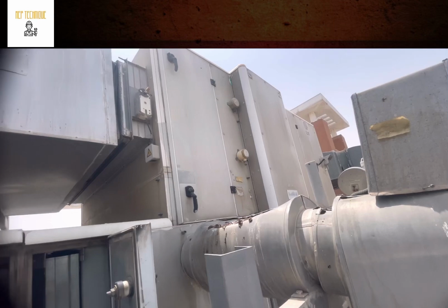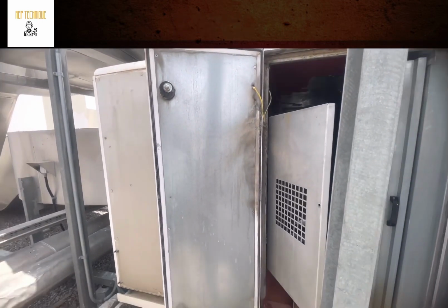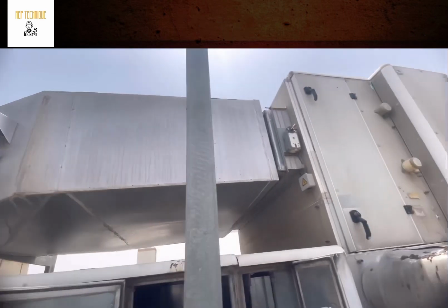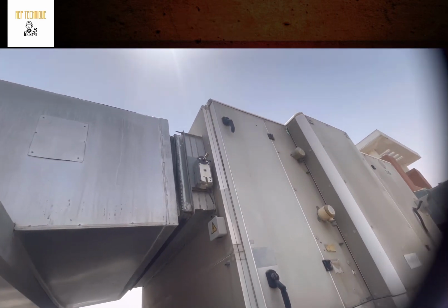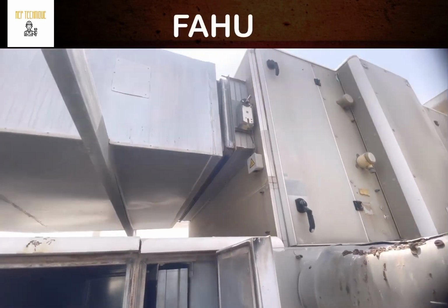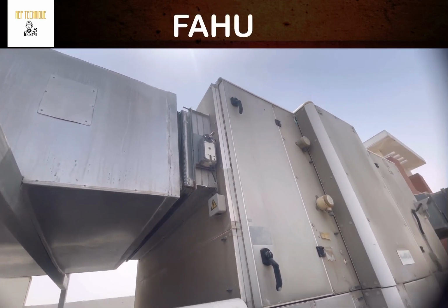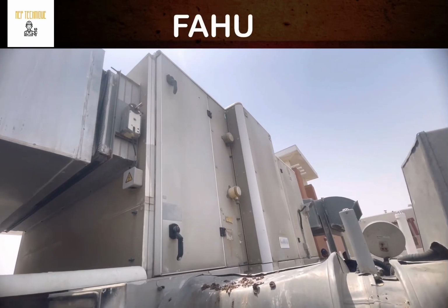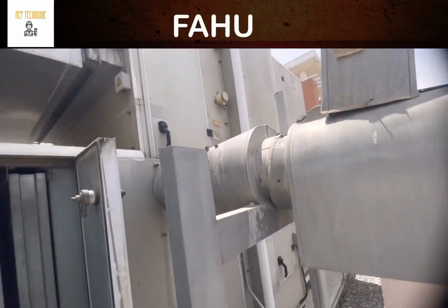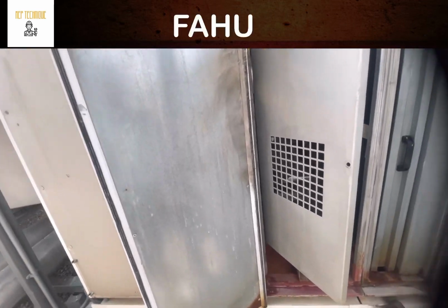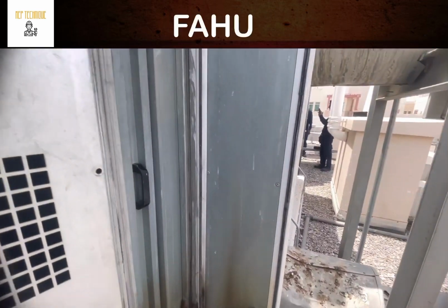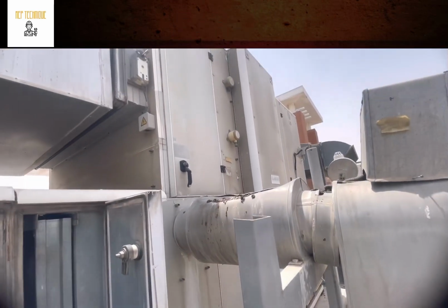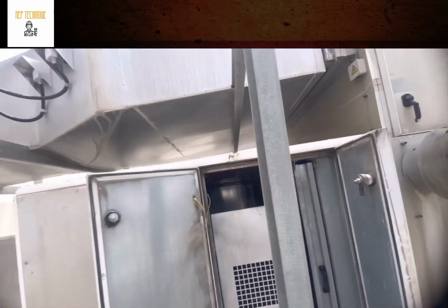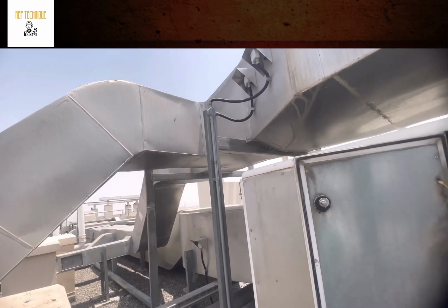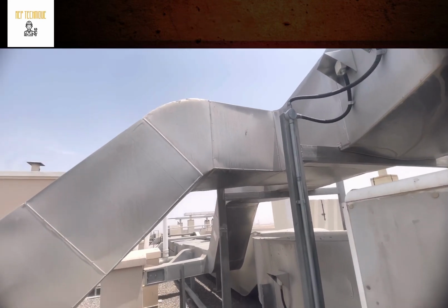Apart from that, there is a DPS, differential pressure switch, which monitors the filter. And also there is a VCD, volume control damper. We can control the airflow with this volume control damper. The upper section is for exhaust air and the lower section for fresh air. This is a fresh air handling unit where we can provide fresh air to our building. As per the standard, each person requires 15 to 20 CFM of fresh air. This is the duct section which is connected to the building.